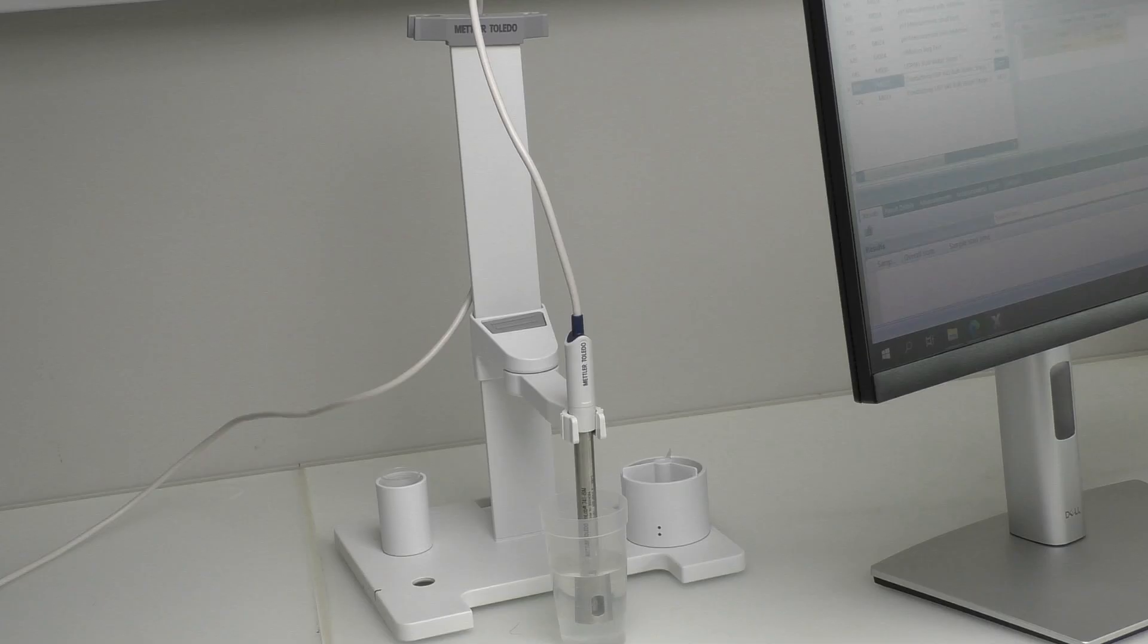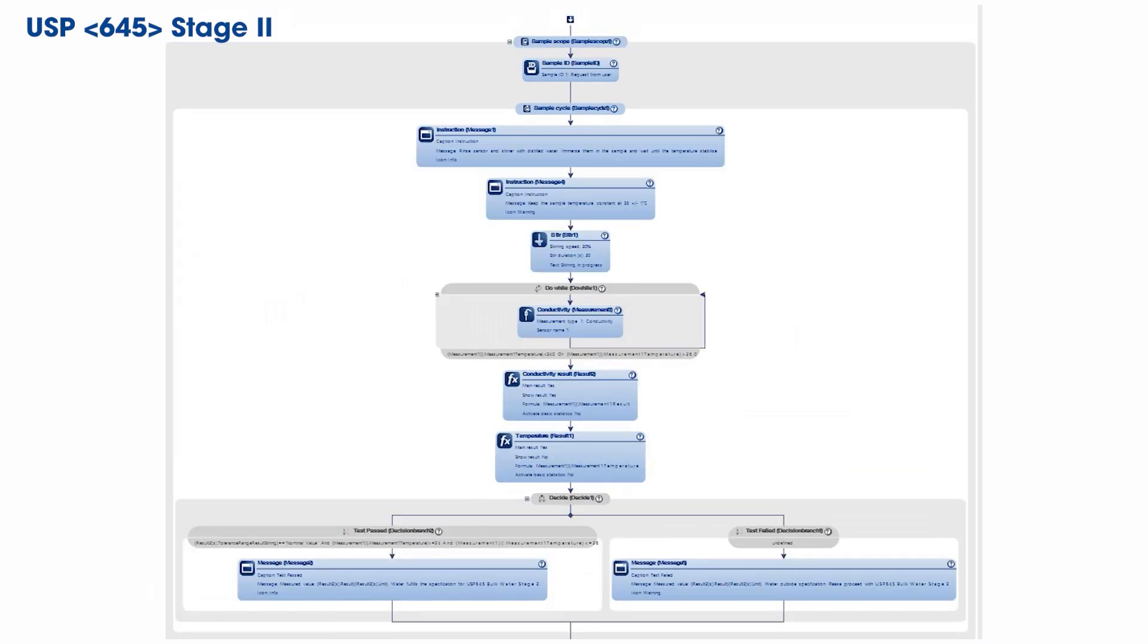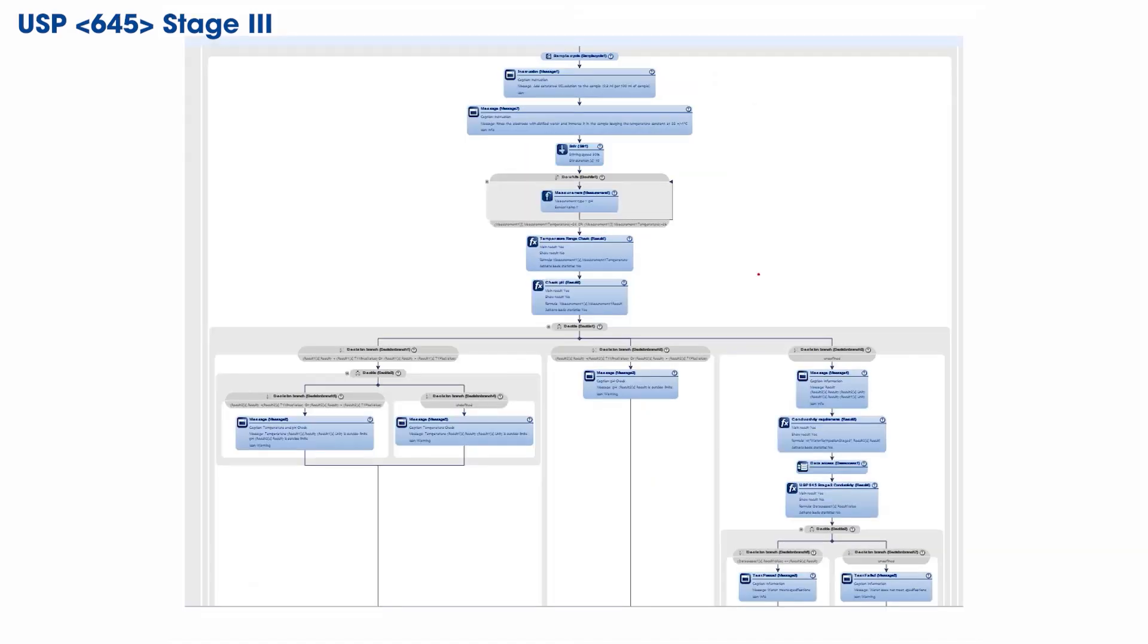For new sensors or ones not used for a long time, we recommend conditioning the sensor for at least 30 minutes in deionized water. The LAB-X method for USP645 is built with the three stages that must be performed sequentially in case of a failed sample result.